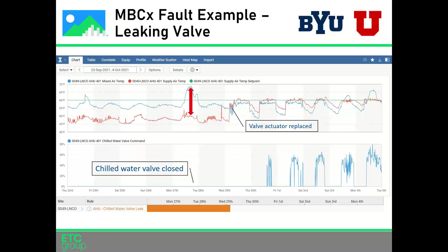Okay, the second example comes from BYU. They have a life science building that has a vivarium. So it's a really sensitive, critical space, a really important place to keep and maintain proper environmental conditions. What we noticed here is that the air handler providing conditioning to this space was having a little bit of an erratic temperature. The pink line is the actual temperature, and the green is the set point. As you can see at the bottom here, these little orange blocks represent the faults that were being detected by the software, showing that it wasn't meeting its discharge temperature.